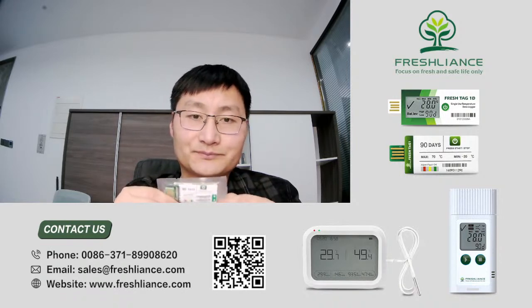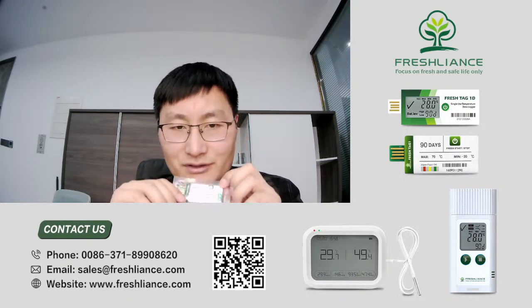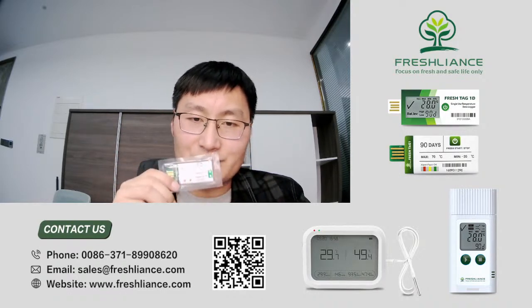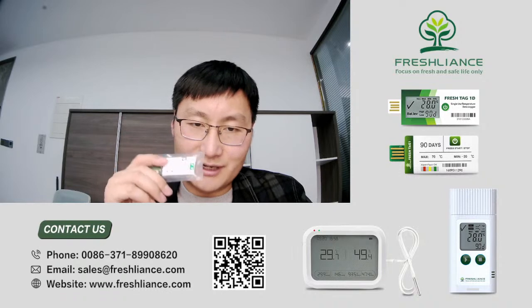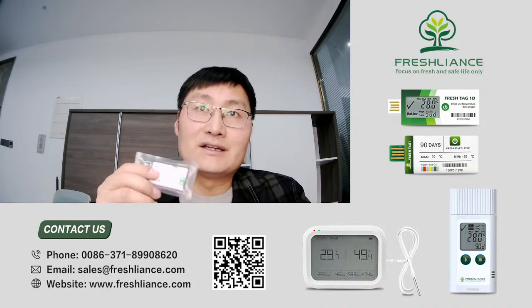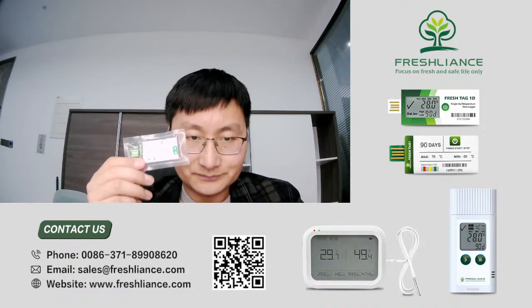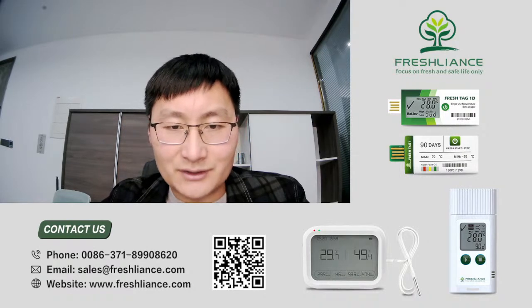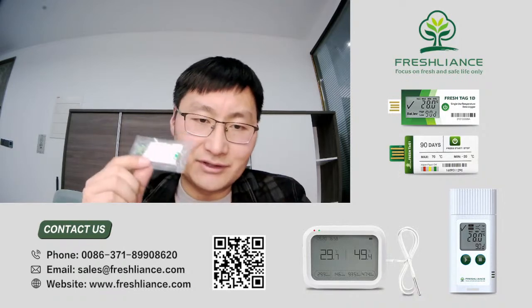This is our advantage compared with other brands of data loggers. The temperature accuracy is plus minus 0.5 degree at full temperature scale. For working days, maximum we can do 300 days. Usually customers will need only about 30 or 60 or 90 days. Memory capacity maximum 129,000 readings. And the display is only 3 LED indicators.